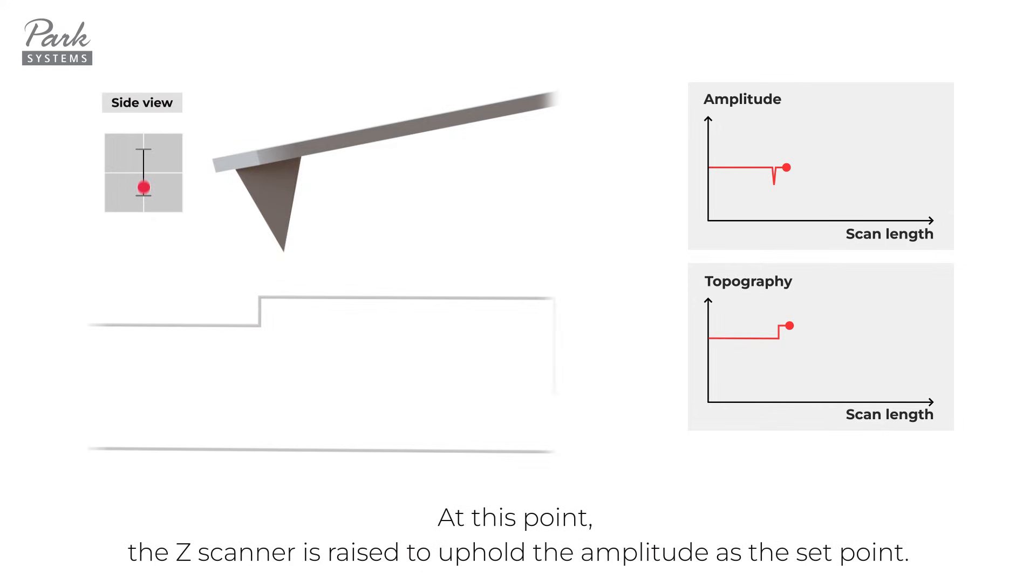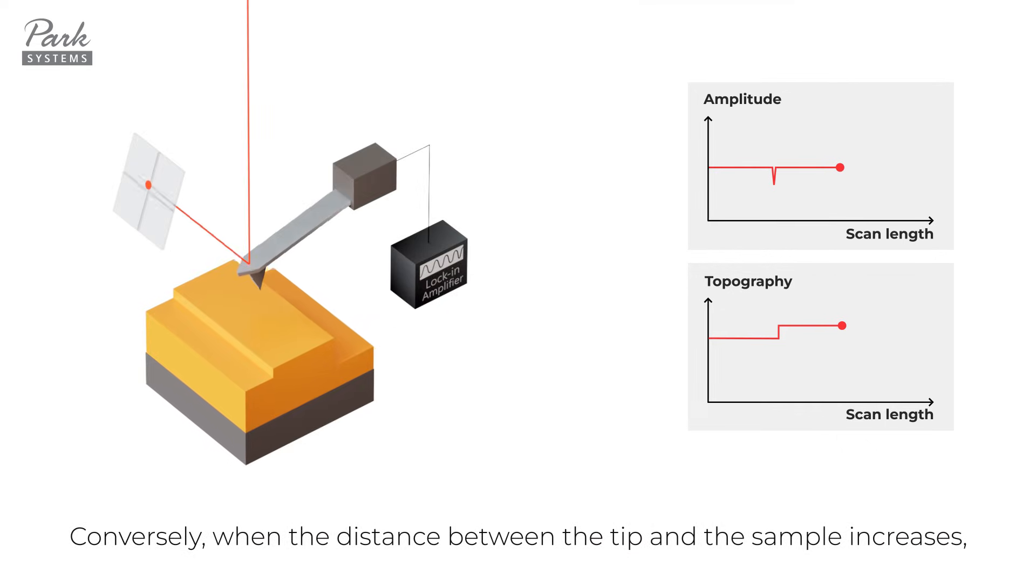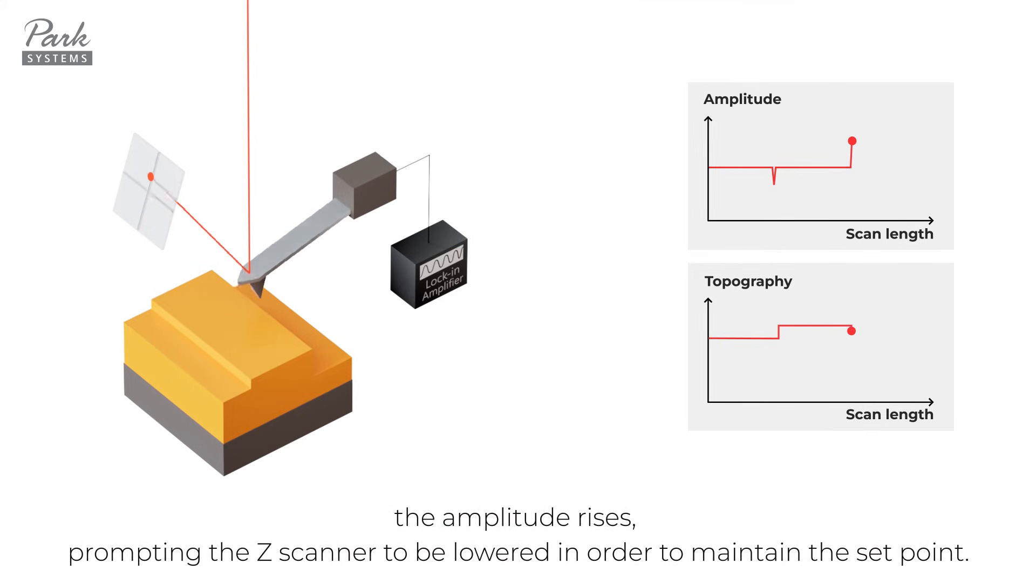At this point, the Z-scanner is raised to uphold the amplitude as the set point. Conversely, when the distance between the tip and the sample increases, the amplitude rises, prompting the Z-scanner to be lowered in order to maintain the set point.